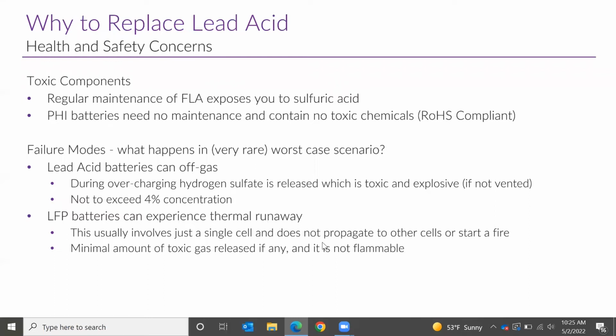Now, lithium iron phosphate batteries are not the same as all lithium batteries. Lithium iron phosphate is a much more thermally stable, much safer chemistry. So even if you do manage to force one of the cells into a thermal runaway event, it's very difficult for that cell to actually release heat quickly enough to affect the other cells in the bank. We've actually tested this—the Underwriters Laboratory, also known as UL, has performed the 9540A tests on our products.